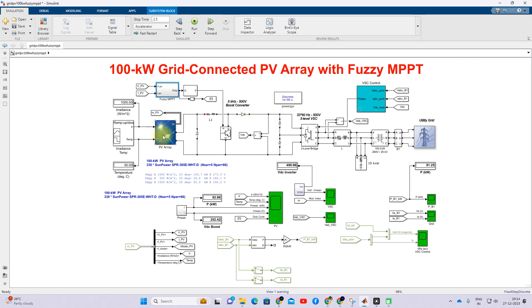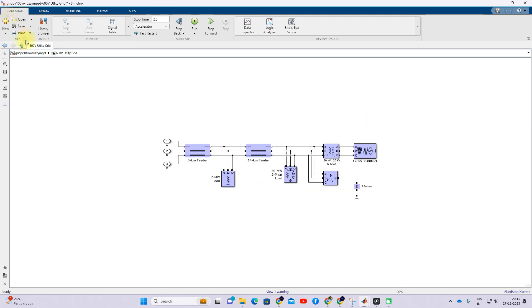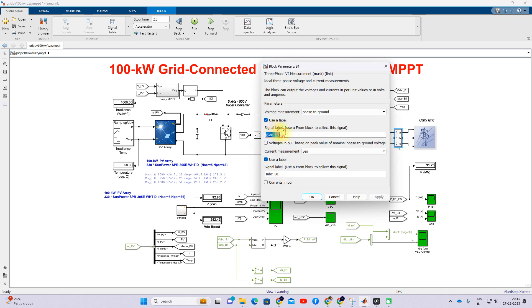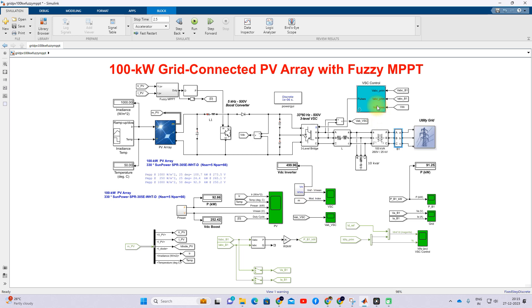Next is the inverter control. After the inverter we have an LC filter, and then a step-up transformer that transforms the voltage from 260 volts to 20 kilovolts, which is then connected to the utility grid. For inverter control, after the transformer we measure the voltage and current, and we also measure the DC link voltage, applying the decoupling control concept.